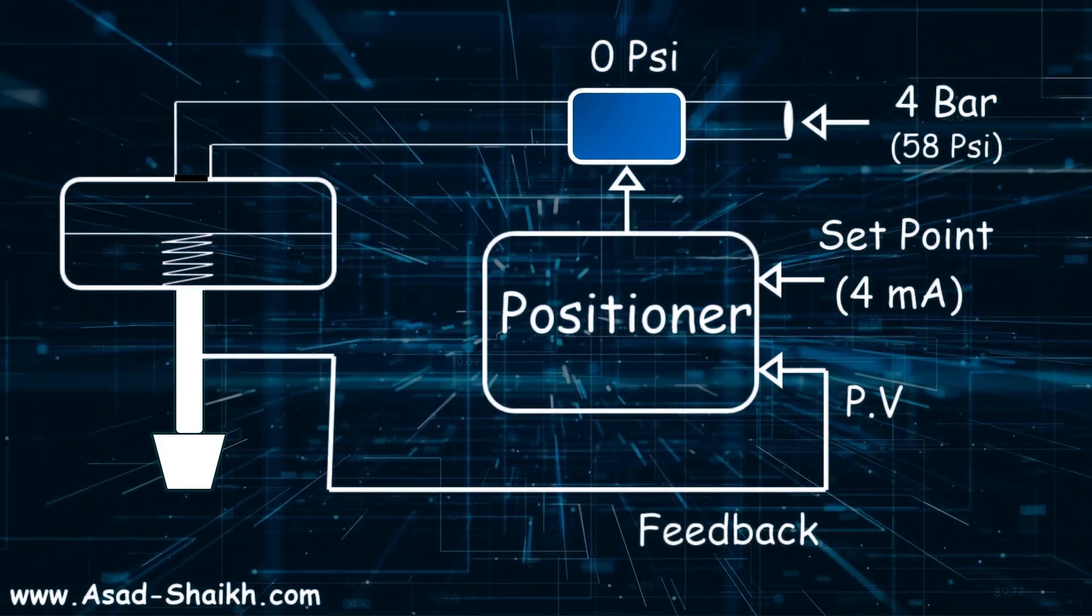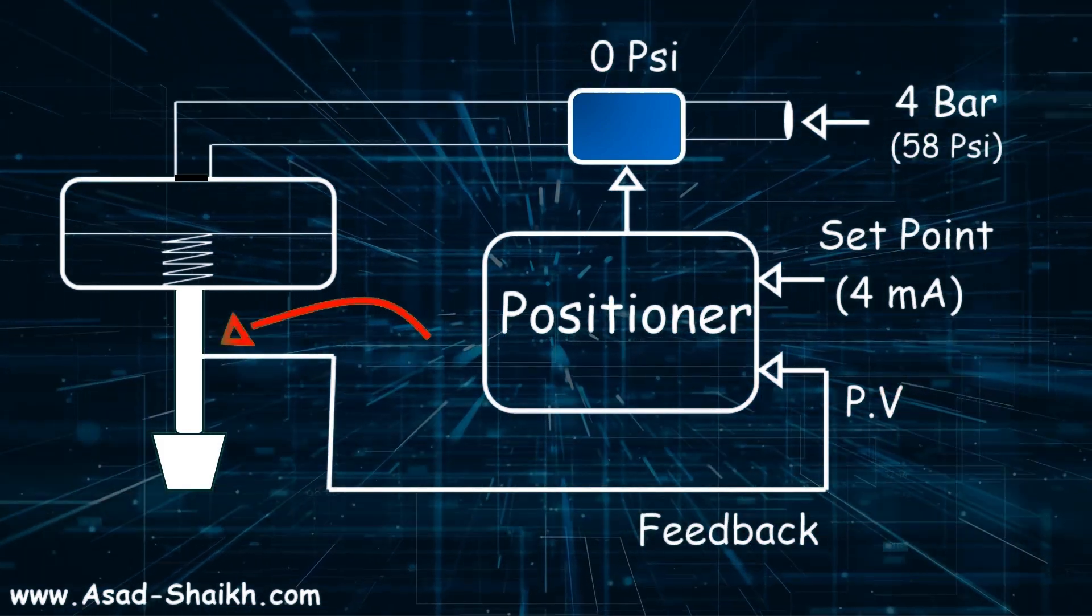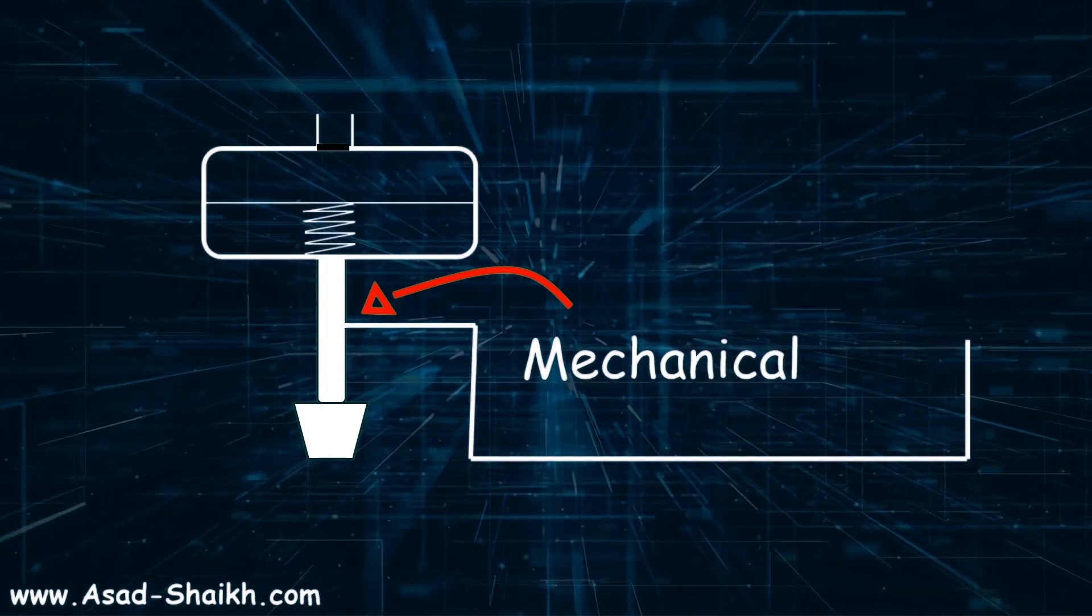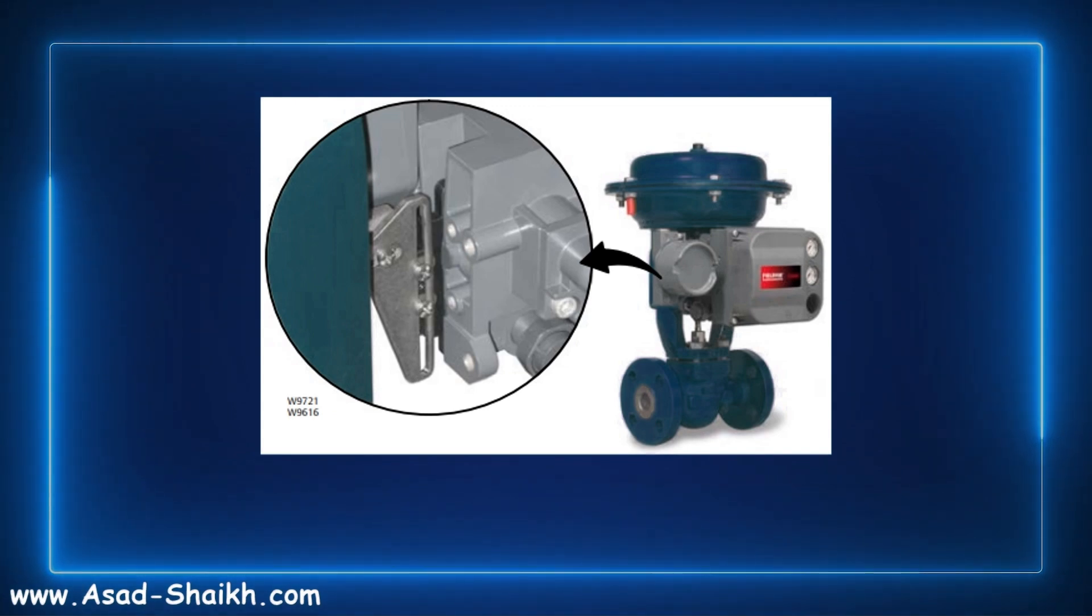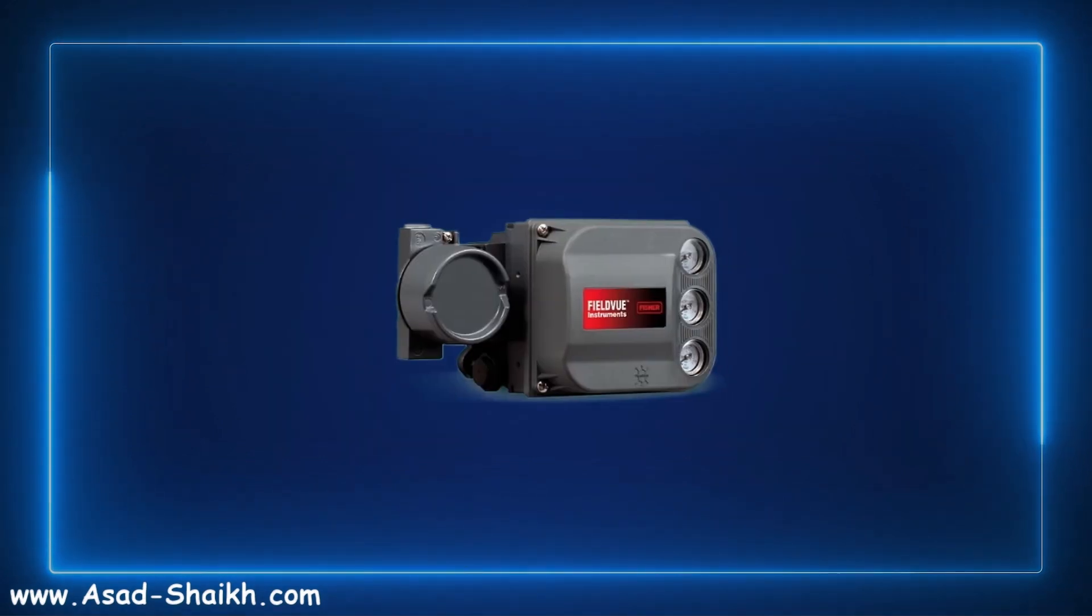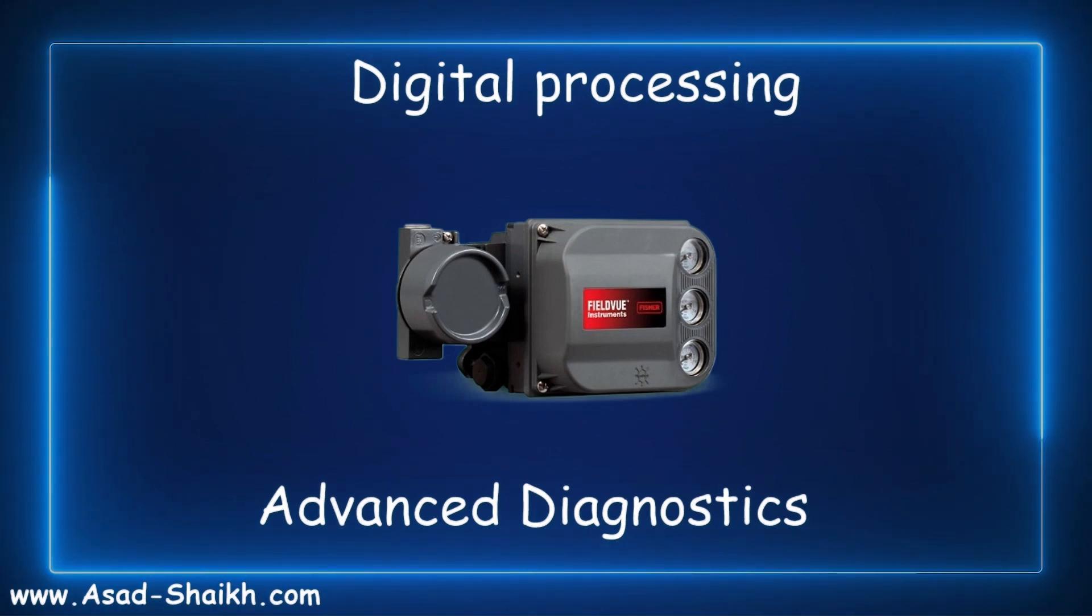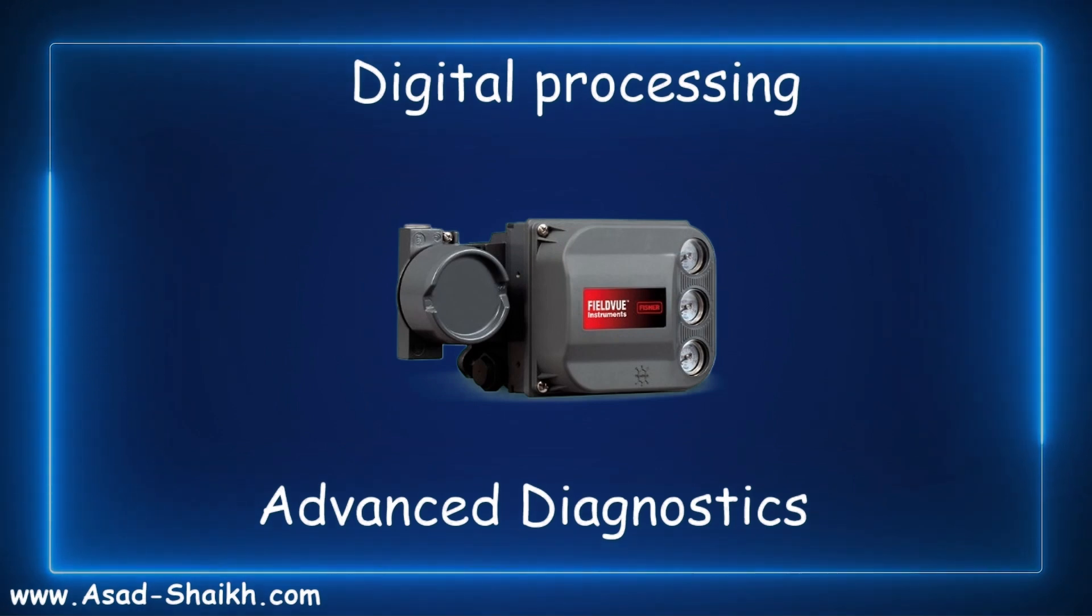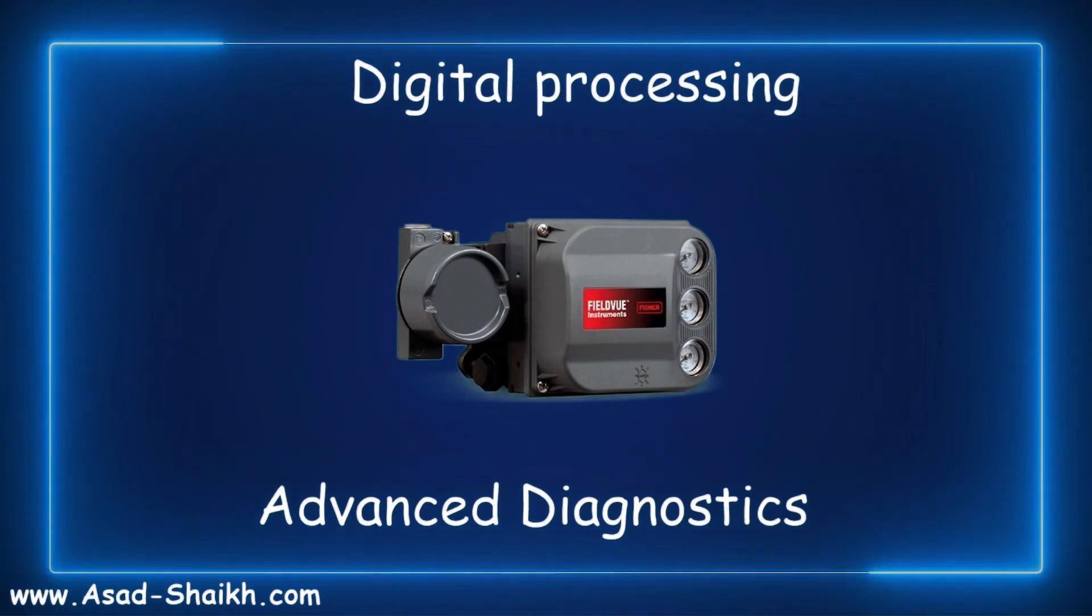But there have been a lot of advances in positioner systems. For example, this mechanical linkage is obsolete. Most of the positioners that now come in the market have linkage-less connection. For example, this is the Emerson control valve positioner where there is a linkage-less connection available. Notice that the positioners now have digital processing and advanced diagnostics, so you already get to know beforehand whether the controller is going to fail, is the packing going to fail, is there fugitive emissions happening, or any other issues can easily be diagnosed before even the control valve failing.